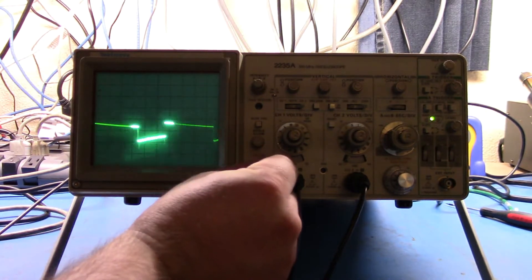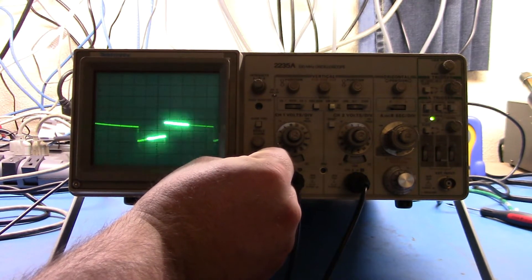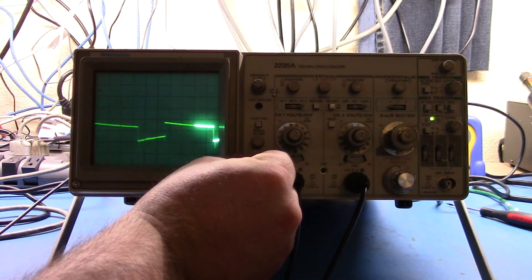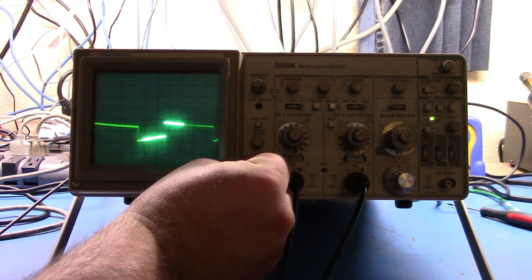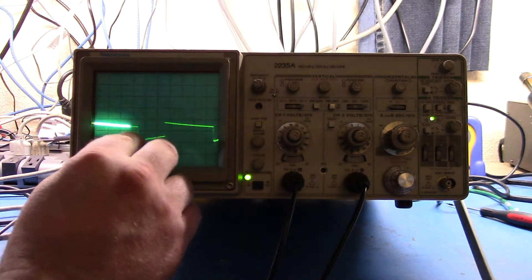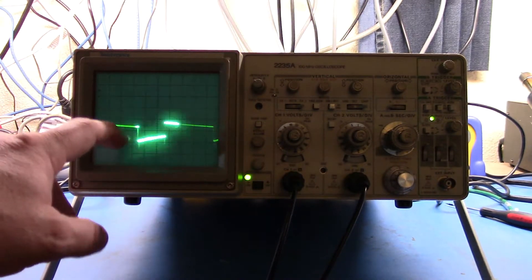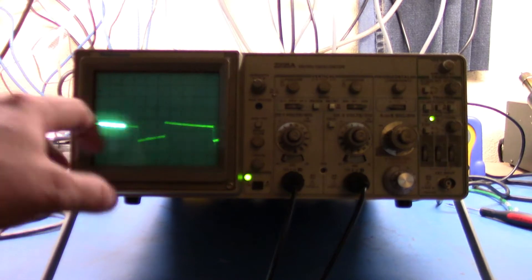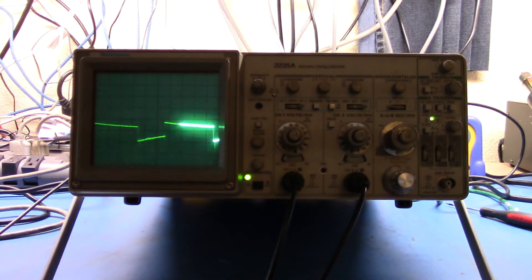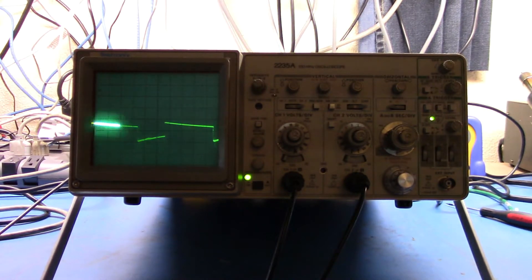Now this is a negative going crystal detector, so the sweep is starting and the sweep is set to run from 10 megahertz to 80 megahertz.